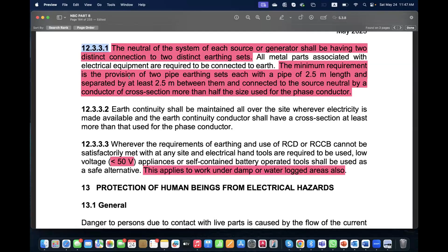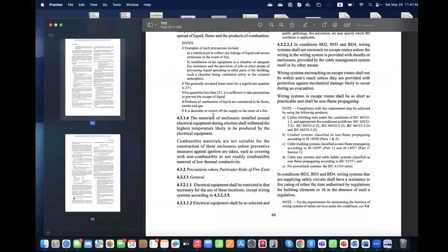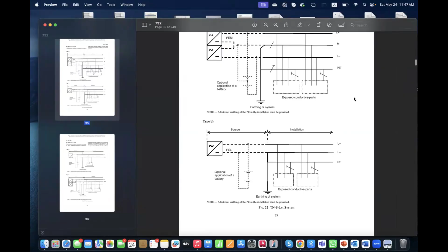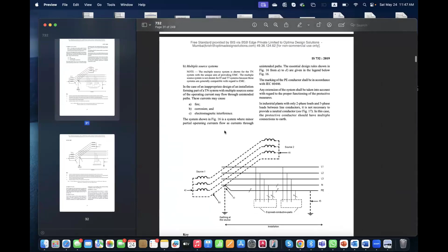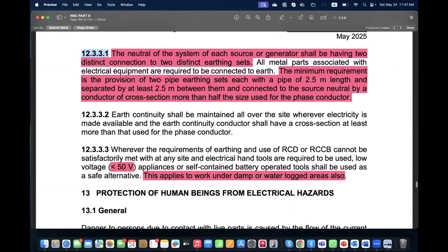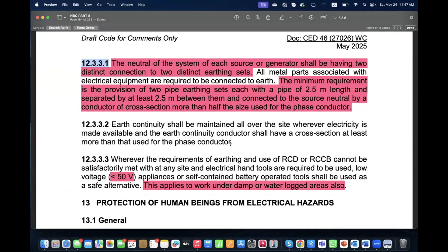This clause 12.3.3.1 is completely in contradiction with the IEC standard and the IS standard. If you look at IS 732, it clearly mentions that you need only one connection between the live parts and the earthing arrangement, and this is clearly mentioned in the section for multiple source systems. But we have not done that here at all. They have just rewritten exactly what was written some decades ago.